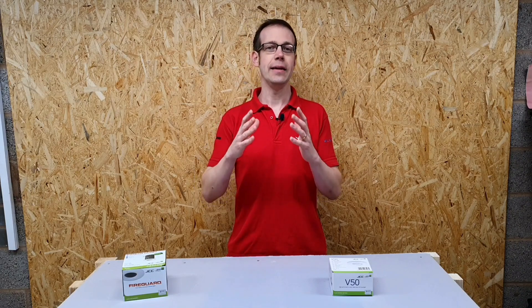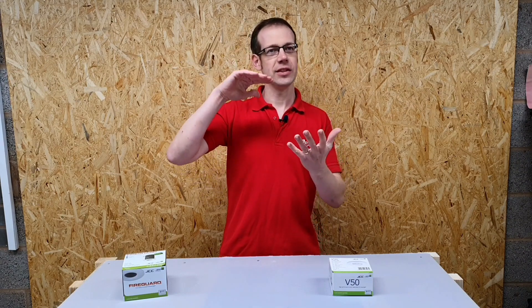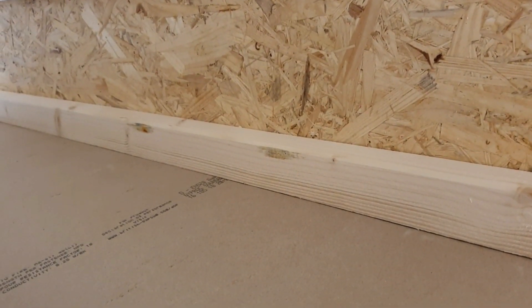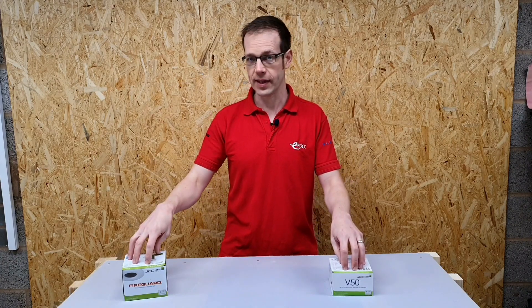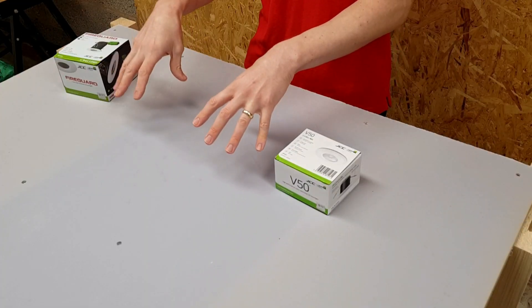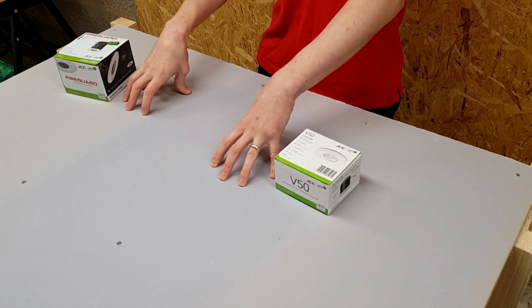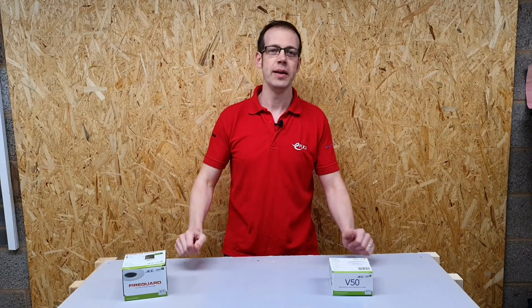So when you think about it in those terms, what we're actually talking about is a system of construction — made up of the joists, the flooring on top, the plasterboard underneath, and any light fittings installed there as well. If you think about this subject as being about a system of construction rather than just light fittings, then it starts to make sense why it becomes the electrician's problem. As soon as you pierce through that plasterboard to put your light fitting in, you start to change and become part of that system of construction, and therefore you've got to make sure your work complies and doesn't damage the integrity of that system.